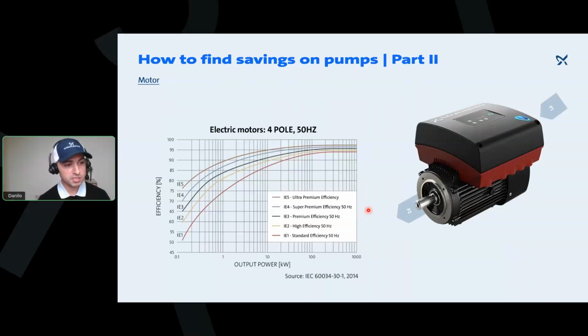What we are introducing here to the market is ECM, permanent magnet motors. That's the best way here, which in the United States is how we call it, like in Europe we have the IE standards, right? So it would be considered an IE5. Here, it's not, I guess, standardized yet. It's not yet a certification in the United States, but you'd be classified as some ultra premium efficiency. So as you can see on this graphic, right, how efficiency goes up compared to the output power. You see the difference of it. So the top line, that's when you have the highest efficiency, permanent magnet motors, whenever possible to utilize this. That's your highest efficiency.